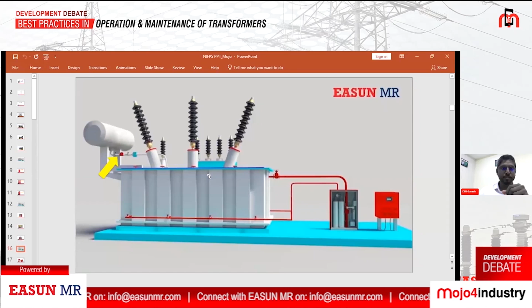See, the arrow which we have shown is a shutter valve. This shutter valve would be placed very near to the conservator. It is placed between the conservator and the Buchholz relay. In case of any fire incident, first we drain 10% of the transformer oil, and the conservator oil would be stopped by the shutter valve itself.